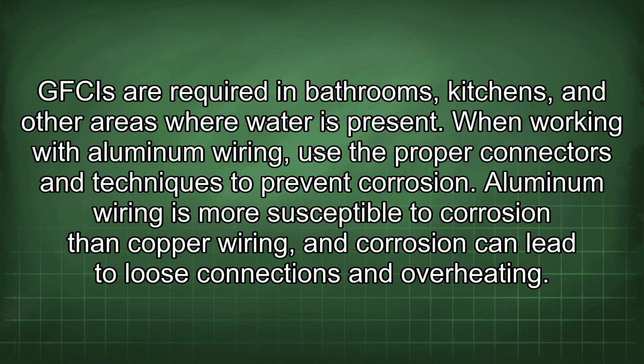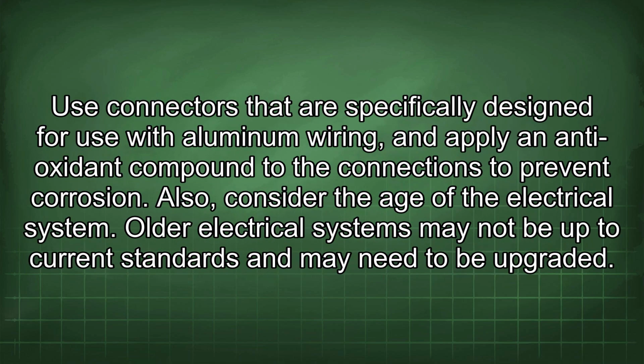When working with aluminum wiring, use the proper connectors and techniques to prevent corrosion. Aluminum wiring is more susceptible to corrosion than copper wiring, and corrosion can lead to loose connections and overheating. Use connectors specifically designed for aluminum wiring, and apply an antioxidant compound to the connections to prevent corrosion.